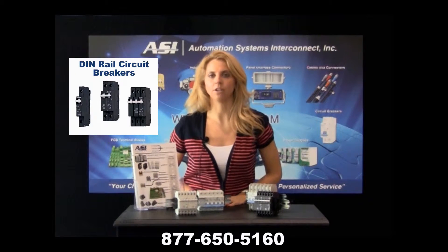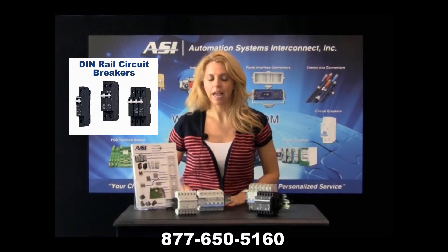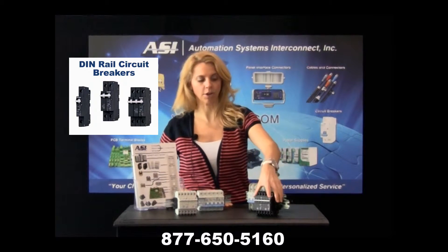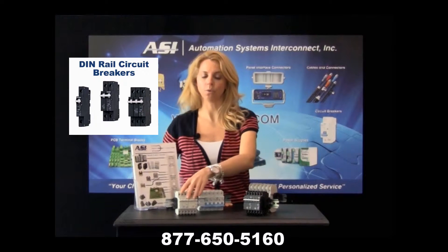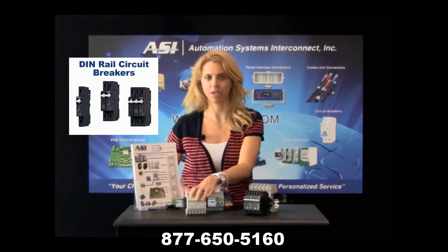Typical UL489 and UL1077 circuit breakers are 18 millimeters wide. ASI has a circuit breaker in both UL489, UL1077, and UL489A that are 13 millimeters. This will save 30% of space on your DIN rail.